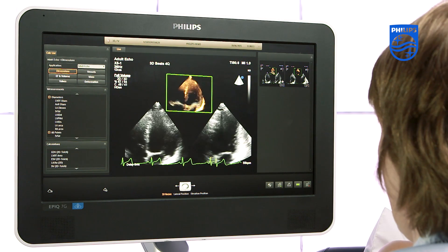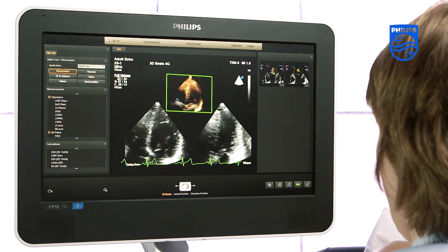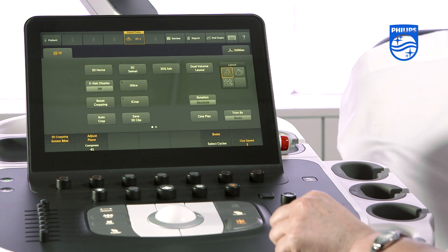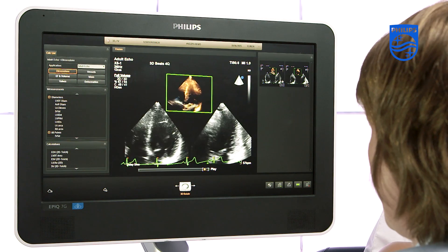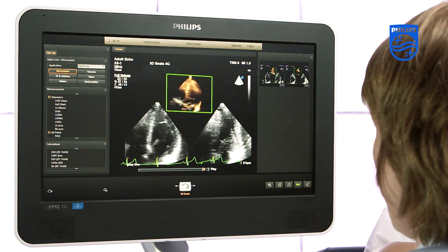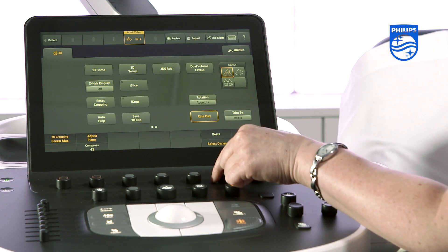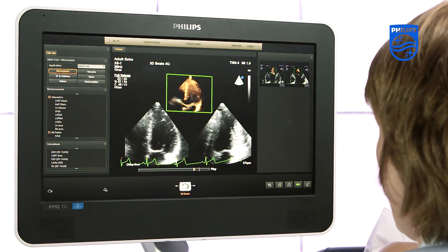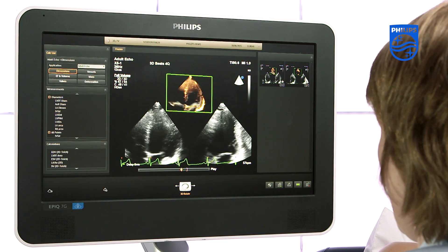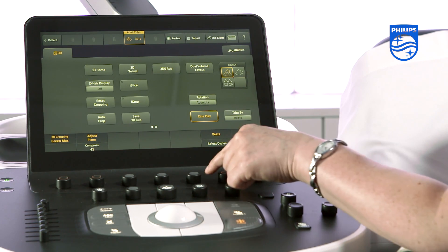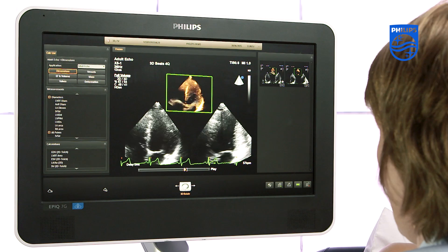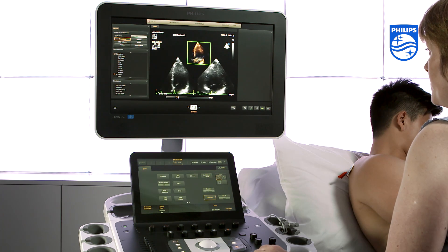The benefit of freezing the data and then replaying the loop is that you get multiple volumes in the buffer. Press freeze and then press cine play and trim by beats. You will see a two-loop volume and can now rotate to select cycles, choosing which two-loop volume you want to acquire. To increase or decrease the loop length, select beats and then rotate the button to your desired loop length. This allows us to assess the quality of the data before acquisition, with multiple volumes to choose from the buffer.